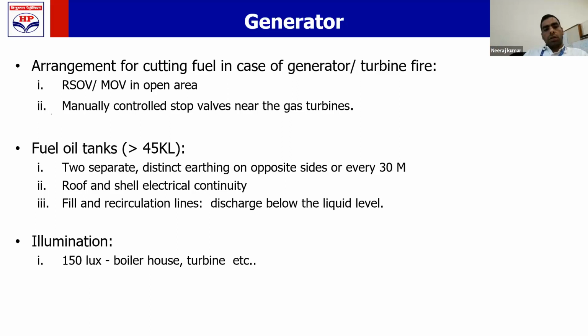Now, if you are receiving fuel from a fuel oil tank, and the capacity of the fuel oil tank is more than 45 kL, then three things need to be taken care of. You need to provide two separate and distinct earthing connections to the shell of the fuel tank. If your fuel tank is of bigger size, which generally may not be there, but if at all your fuel is coming from a huge tank, then these earthings shall be available every 30 meters across the circumference of the shell of the tank.